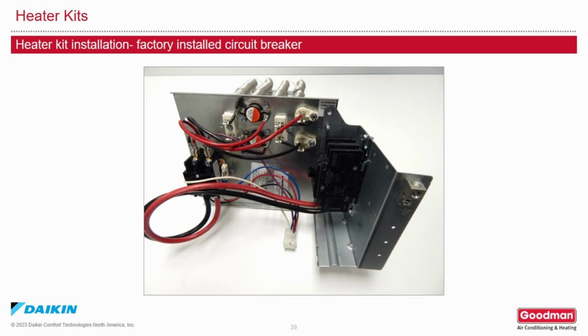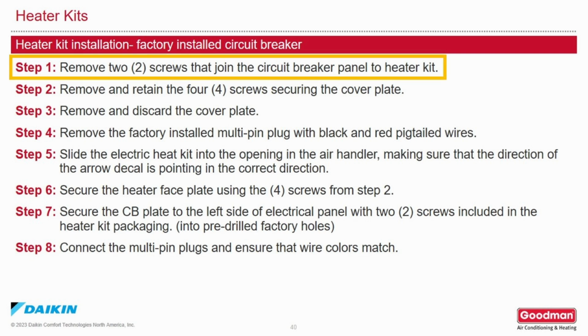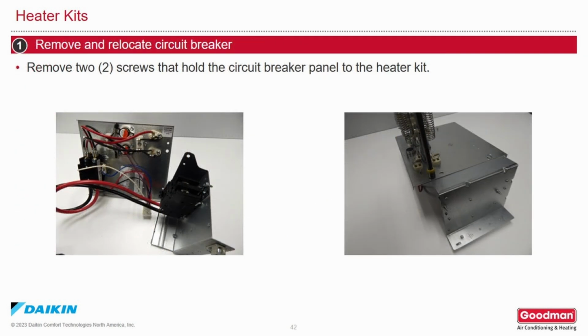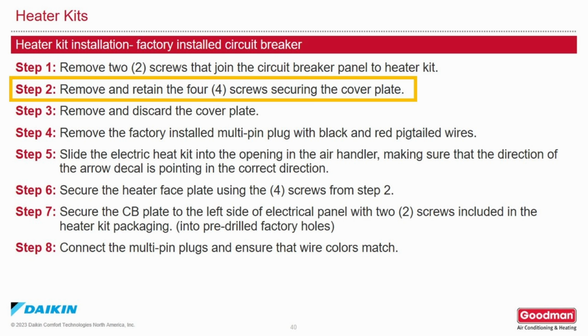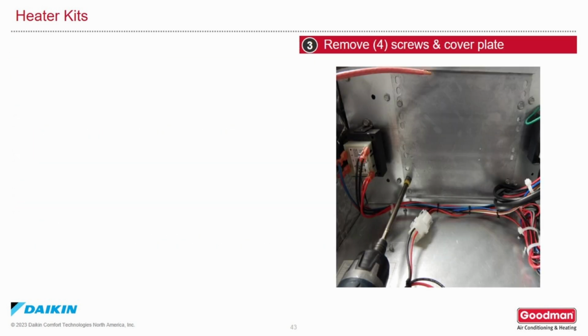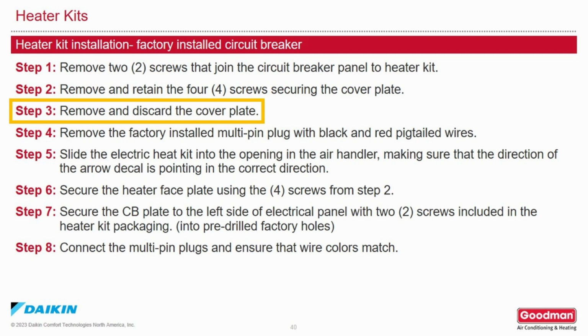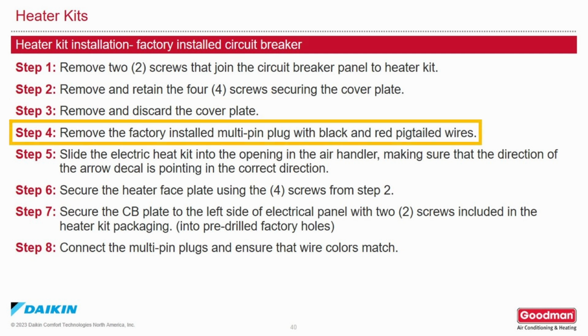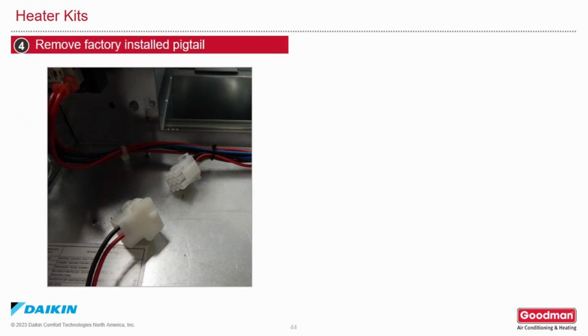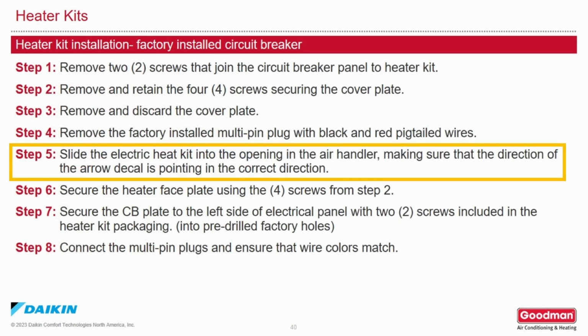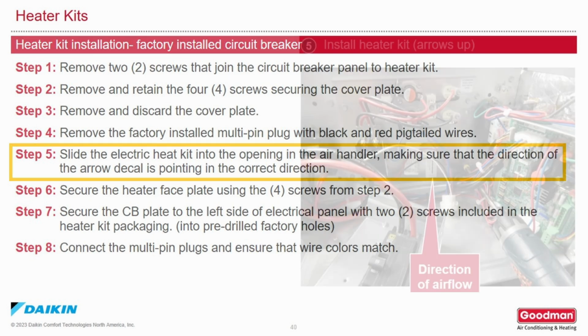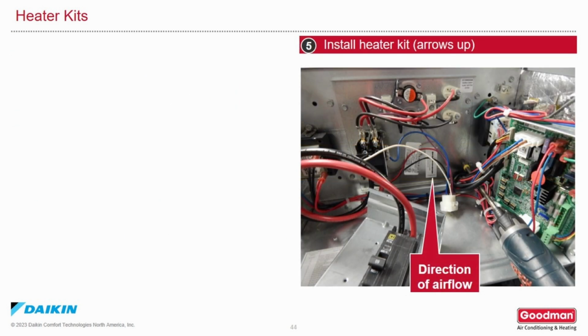Heater kit installation with the factory installed circuit breaker. Remove the 2 screws that connect the circuit breaker panel to the heater kit. Remove and keep the 4 screws securing the cover plate. Remove and discard the cover plate. Remove the factory installed multi-pin plug with black and red pigtailed wires. Slide the electric heater kit into the opening of the air handler, making sure that the direction of the arrows is pointing in the correct direction.